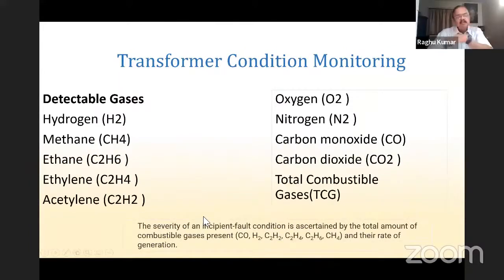These are the gases which we normally detect during condition monitoring. There are 9 gases that I talked about: hydrogen, methane, ethane, ethylene, acetylene, oxygen, nitrogen, carbon monoxide, carbon dioxide, and then total combustible gases are calculated. These combustible gases are carbon monoxide, hydrogen, acetylene, ethane, ethylene, and methane. The fault intensity is dependent on the total amount of combustible gases.